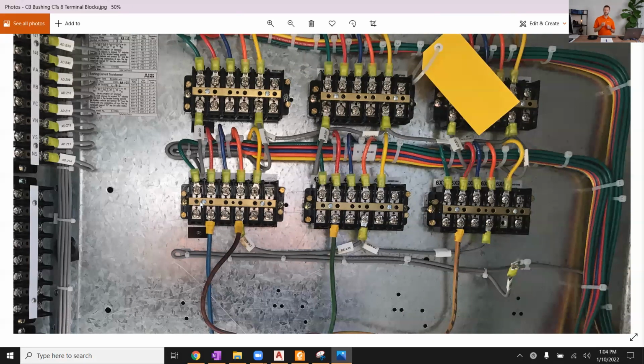You can actually build up quite high voltage, which is a personnel hazard. It can even cause damage to your CT, perhaps, if you have an energized primary system and an open circuited CT secondary system. And so you will commonly find different approaches that we short out the CT secondaries at times. We'll look at that with test switches and terminal blocks later on.